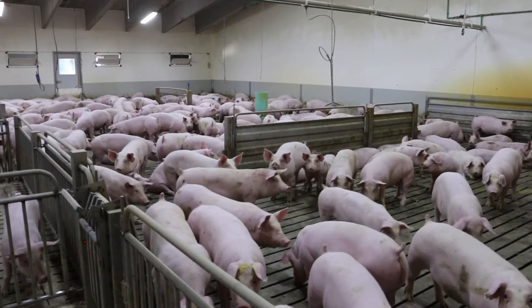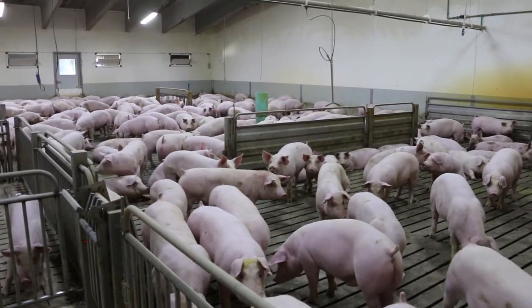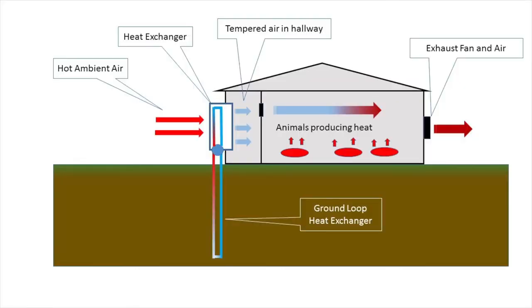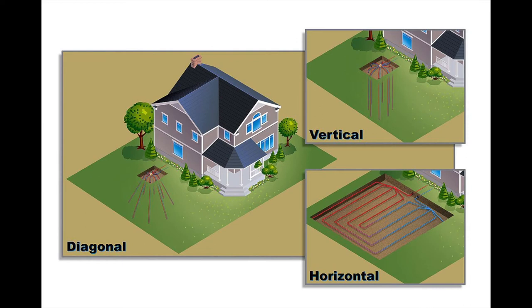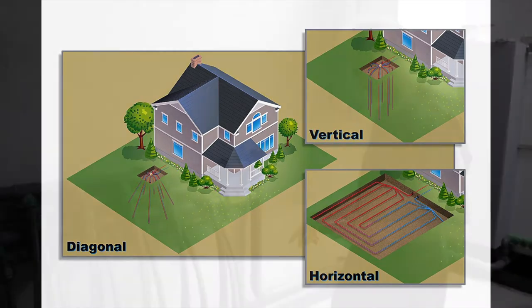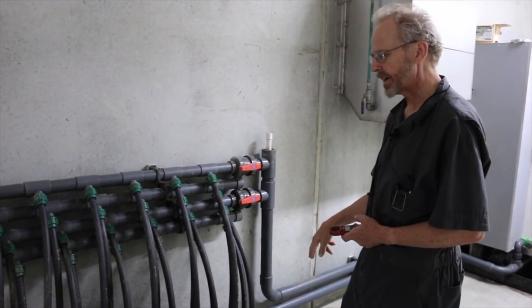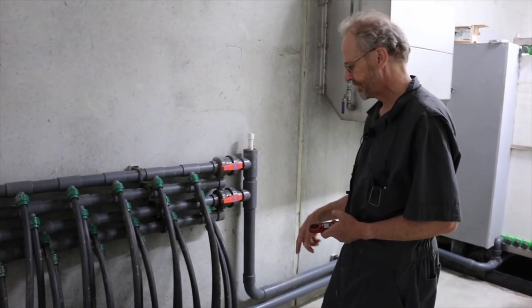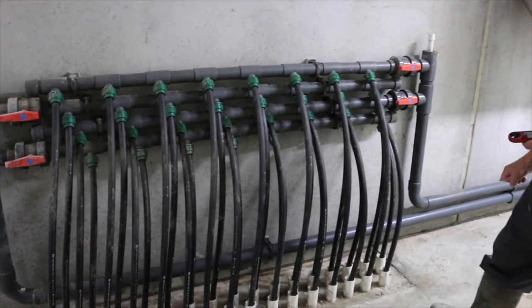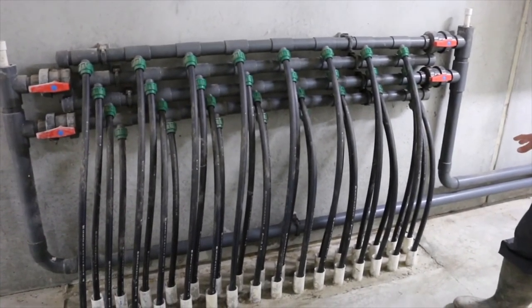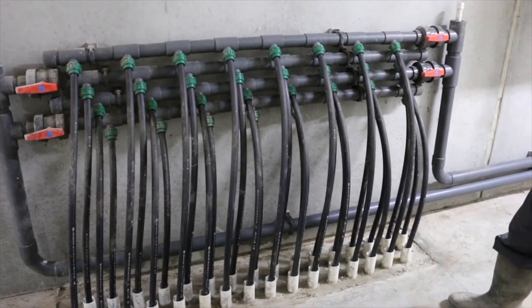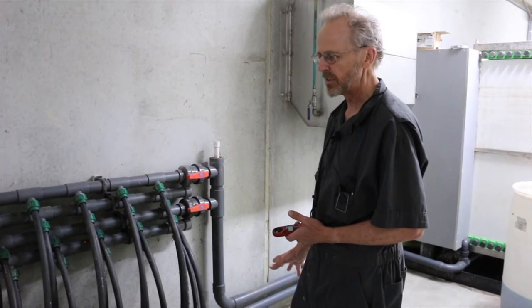Geothermal cooling systems are used to cool the inlet air coming into the barn. In these systems, a water glycol mixture is circulated through a looped piping system in the ground, where the temperature is stable year-round at about 50 degrees Fahrenheit. These ground loops can be vertical, going as deep as 300 feet down into the ground, or they can be installed horizontally at around 15 feet deep. These go down about 230 feet into the ground and come back up. So essentially, once you get down to 10, 15 feet, the geothermal temperature at that level is right around 50 degrees Fahrenheit.